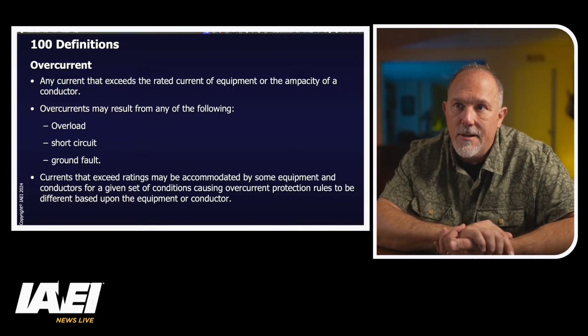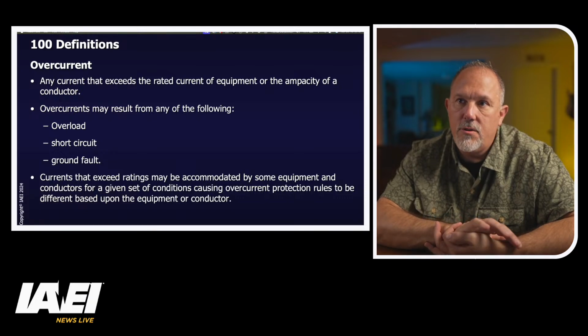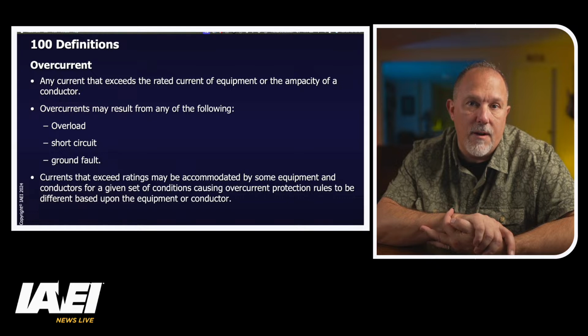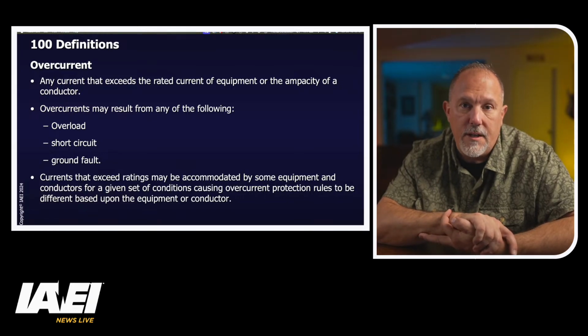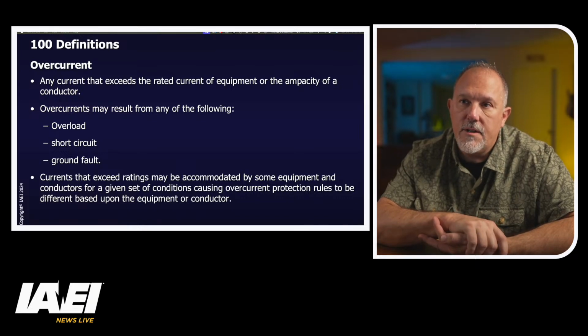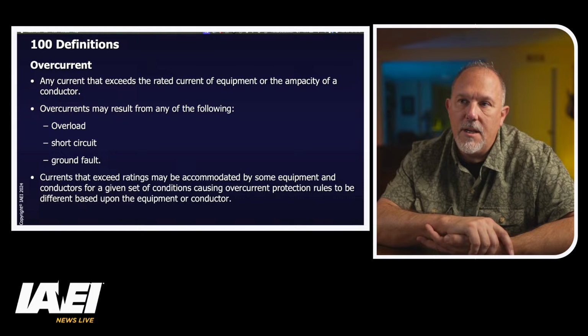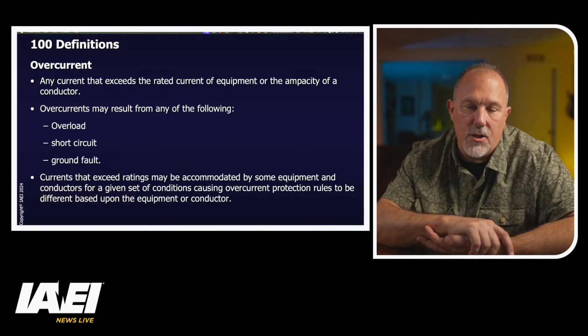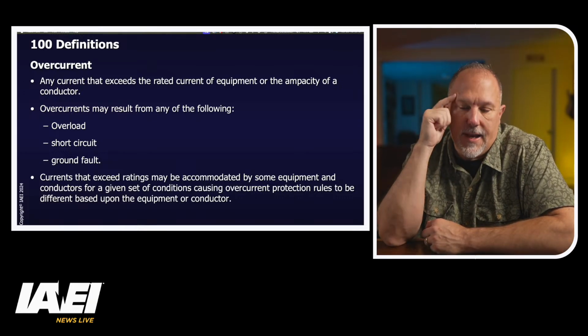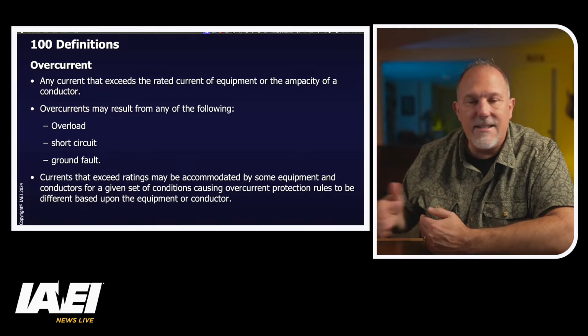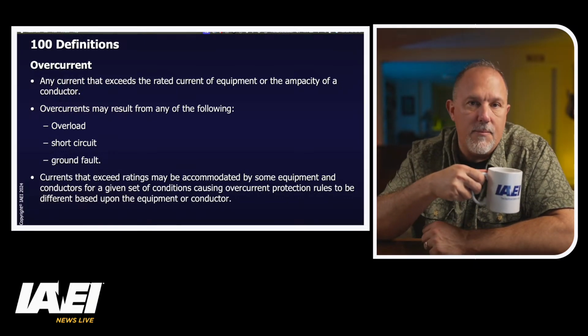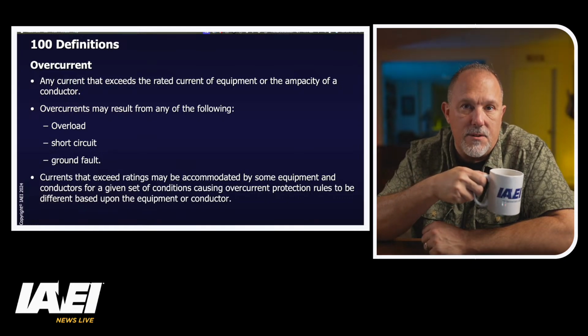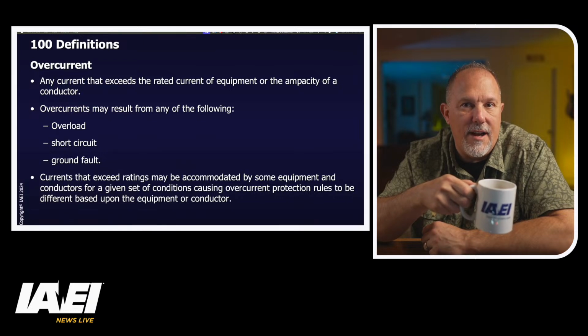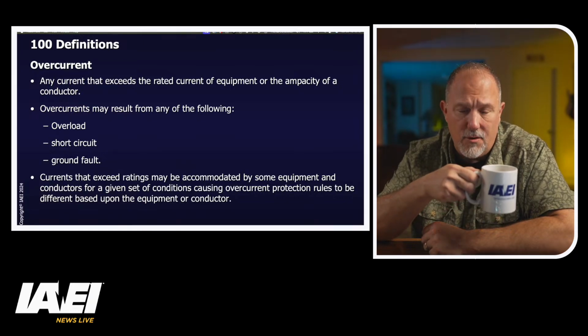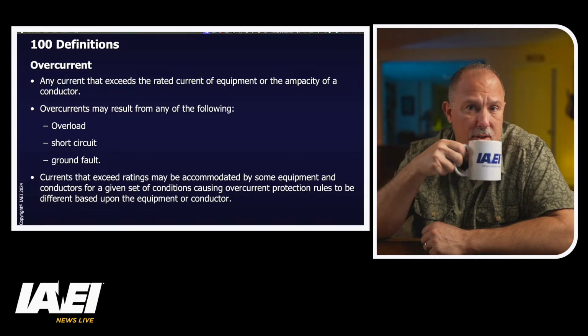So if it's a 20 amp breaker, I can have a ground fault current, which is an overcurrent. It can be due to overloads, short circuits, and ground faults, but the ground fault current has to be greater than the rated current of the device. Makes sense. So currents that exceed the ratings may be accommodated by some equipment and conductors. Remember that in some cases, I can take a temporary overcurrent. I can take a temporary overload as long as it's not persistent. And if it is persistent long enough, I need to make sure that the overcurrent protective device clears the fault before damage occurs.